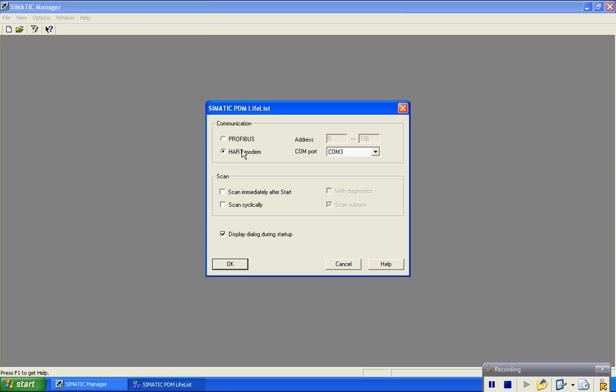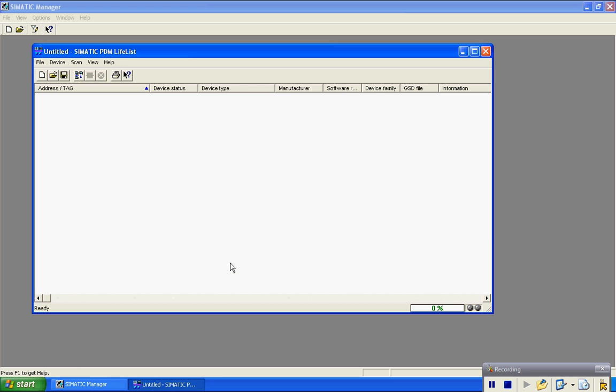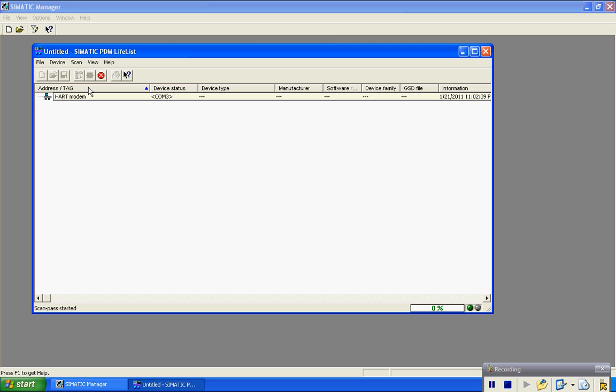As you can see here I have a HART modem hooked up to the transmitter going across the 250 ohm resistor in the loop. We hit OK. We are going to go out and look for this transmitter and do a scan and then a start.